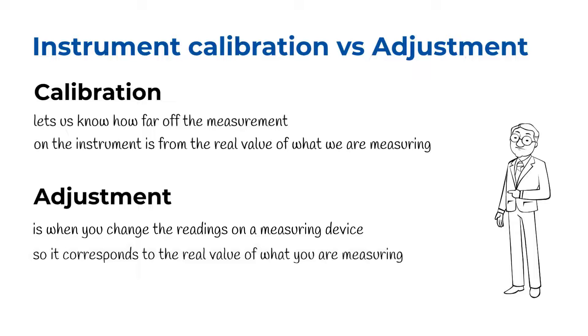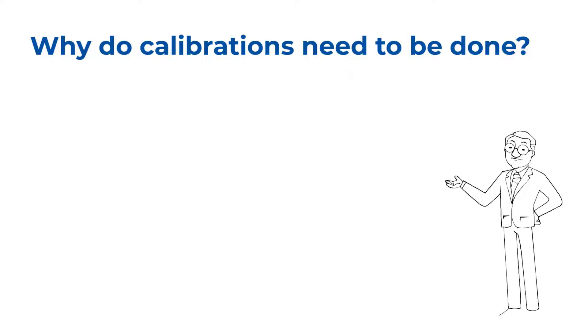Adjustment is when you change the readings of a measuring device so it corresponds to the real value of what you are measuring. This is usually done after calibration.